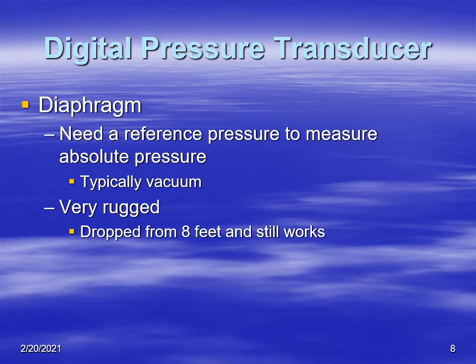For these diaphragms and sensors to work properly, you need to have a reference pressure. Typically, that is a vacuum. In other words, the chamber is evacuated and the membrane is able to flex, but it's rugged enough that it doesn't totally collapse into the sensor. These sensors are also very rugged. I've read some literature that says you can drop one of these sensors from 8 feet and it still works.